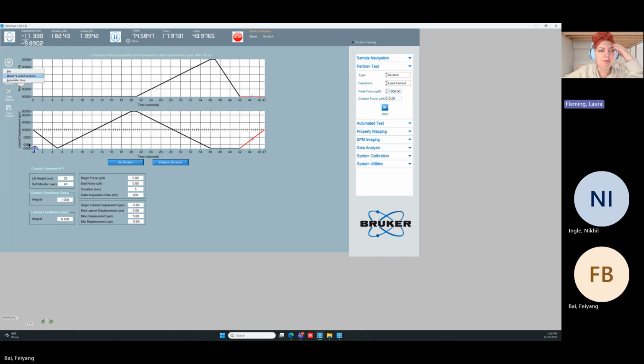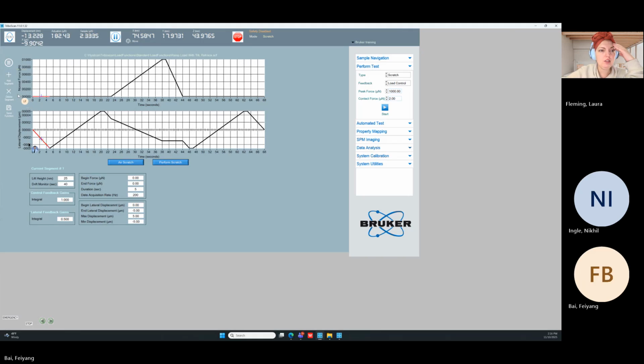When you add the retrace segment, you get this extra portion, this extra 20 seconds at 0 micronewton. What's happening here is that you're doing this again, only it's after the scratch. So you're tracing over where the scratch is. You trace so you can do the tilt, then you do your scratch, and let's say you're really trying to dig out some of the material, trying to make a deep well for some reason, whatever you're testing. Then after the scratch is done, you unload, but then you trace along it again, and that tells you how deep that trough is. So then you have the normal displacement before and after the scratch to tell you how much that normal displacement changed, to tell you how much sample you wore away.